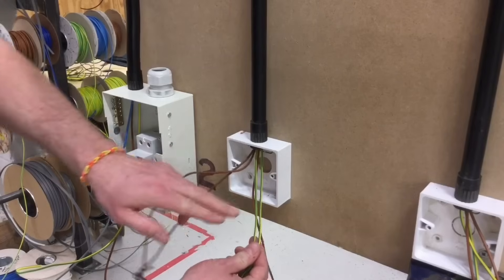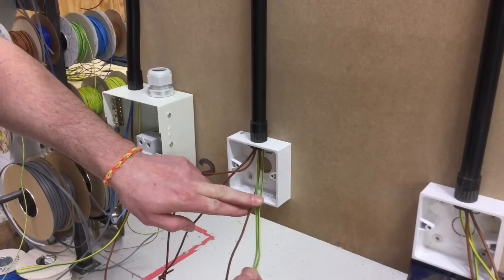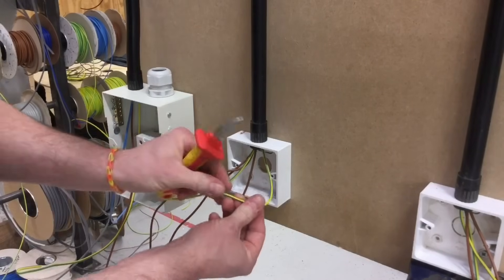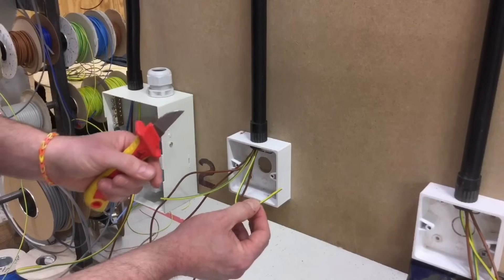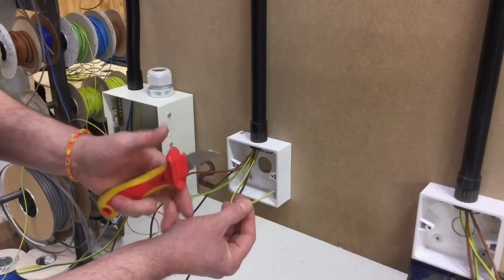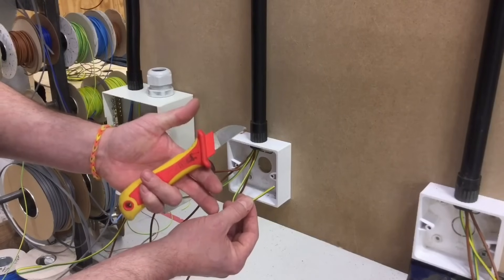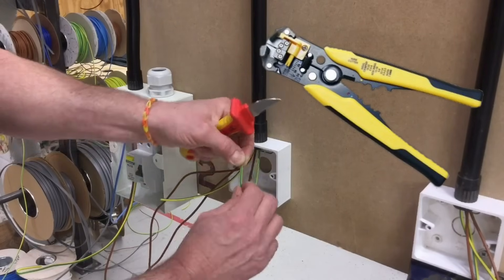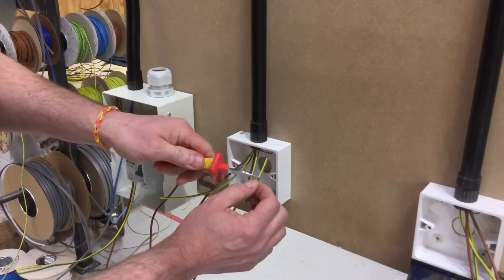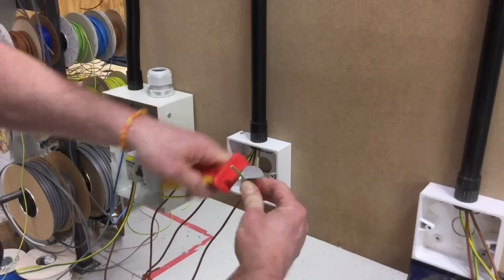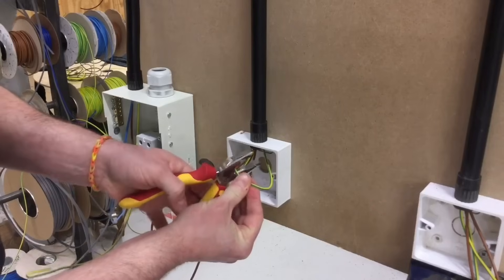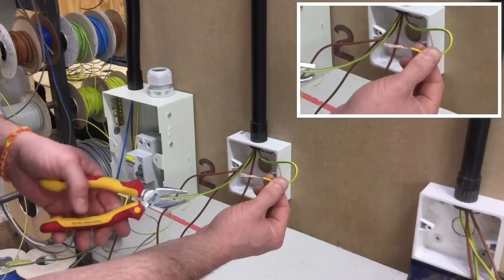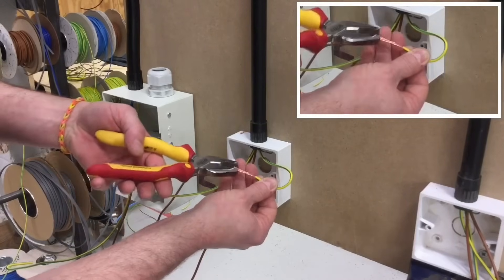We'll start off with my CPCs. As always, we need to make sure they go beyond the box between 50 and 70 millimeters. I'm going to take my knife to remove the outside insulation around the conductors. I know I've taken a lot of stick for this on YouTube - we are early stages of learning, only 14 to 15 weeks. We're trying to get hand skills, so we're going to use a knife. We're not at the stage yet of using any mechanical wire strippers. I'm going to strip it back quite long, score around with my knife, take my pliers and remove the insulation.